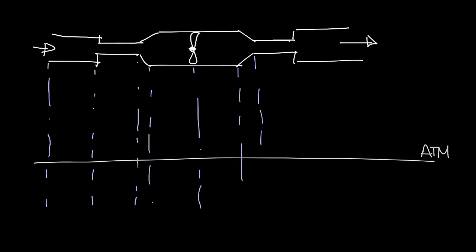Okay, so let's look at the pressure profile of this little piece of ductwork. I'll draw a line down here and that's going to be atmosphere. The air being pulled into the return and the space that's being supplied is just at atmospheric pressure. Now let's draw some lines down to show each of the transitions. Each place that something's going to happen with the pressure will have this little purple line.